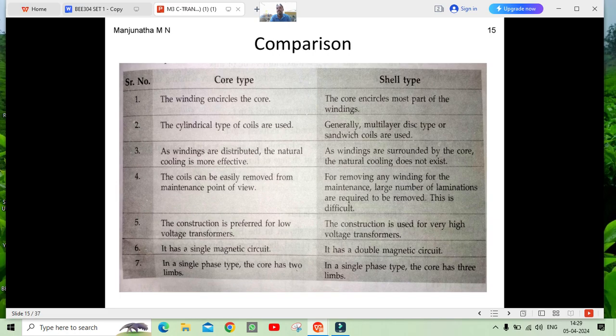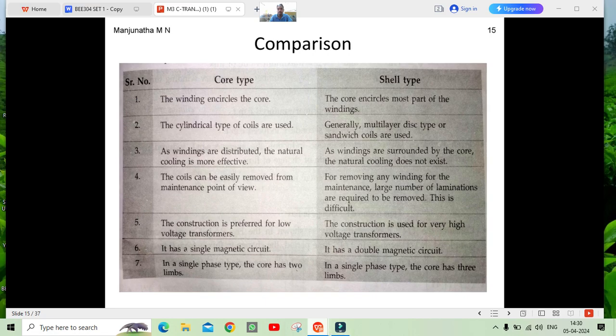In core type, coils are uniformly distributed so natural cooling is effective. In shell type, the center limb contains both primary and secondary windings, so additional forced cooling is required. For maintenance, core type is easy and shell type is difficult. Core type has two limbs and a single magnetic circuit; shell type has three limbs and two magnetic circuits.